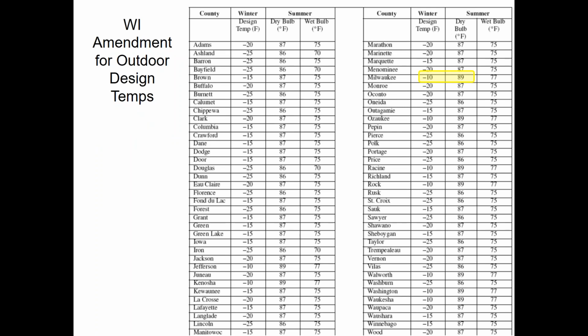Now, what that means for Wisconsin compared to everybody else on this call is if everybody else is doing their load calc and they're doing a good job and getting pretty accurate and they decide to round up a little bit, that's a decision they might make. In Wisconsin, definitely don't do that because you already have added rounding up into the load calc by putting in these incorrect outside air numbers to comply with code.